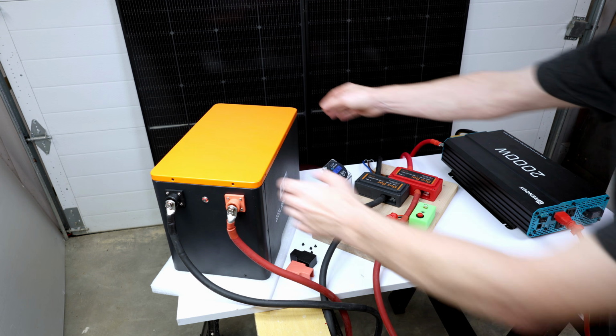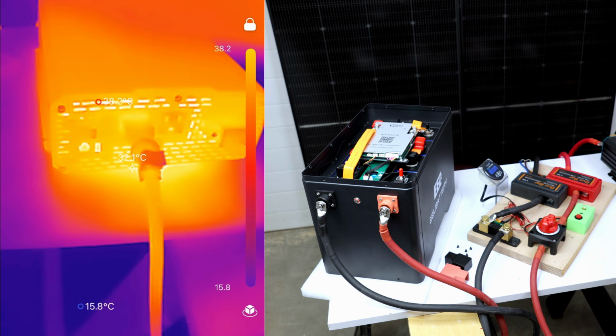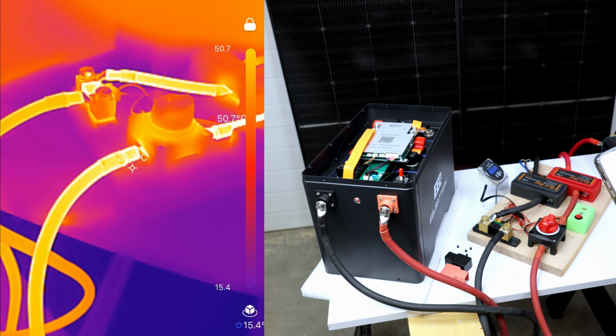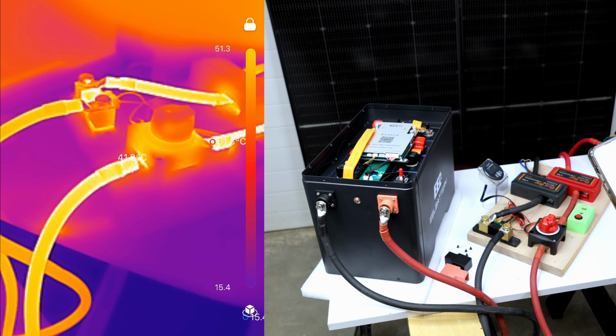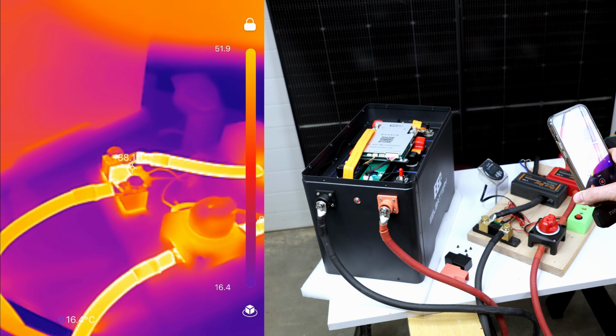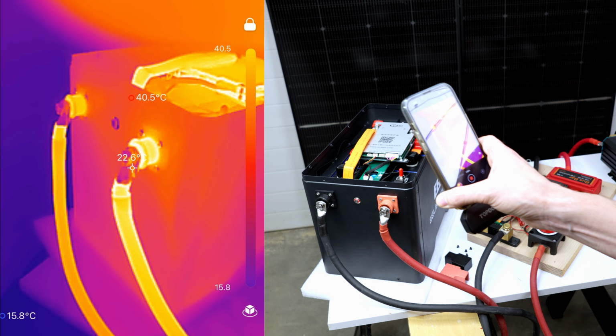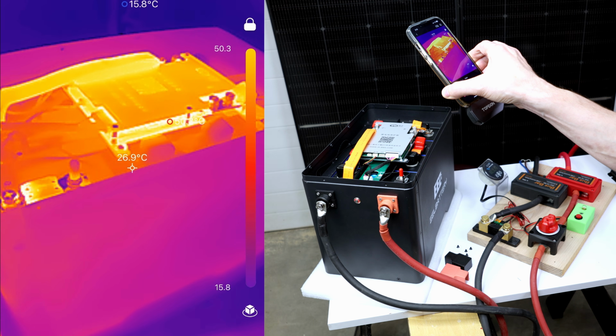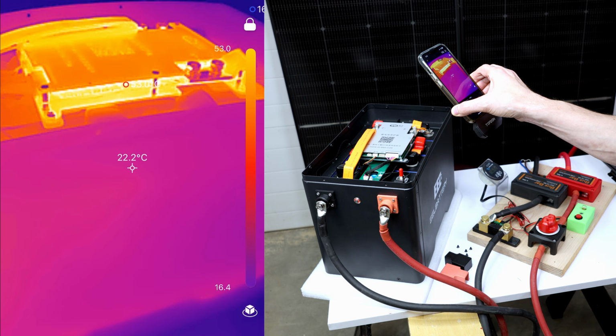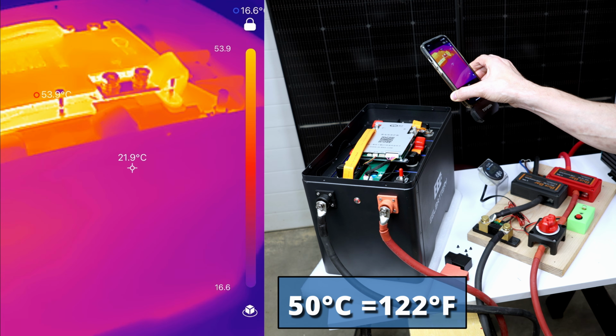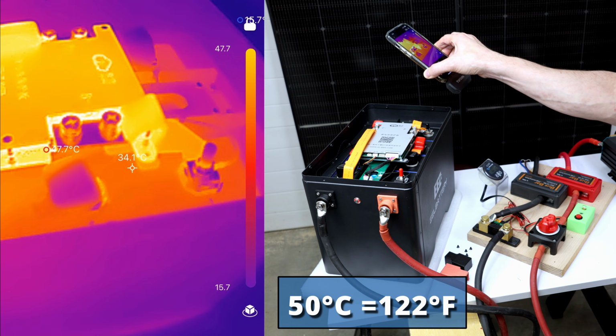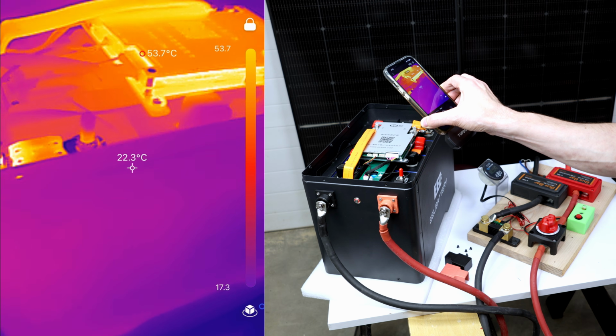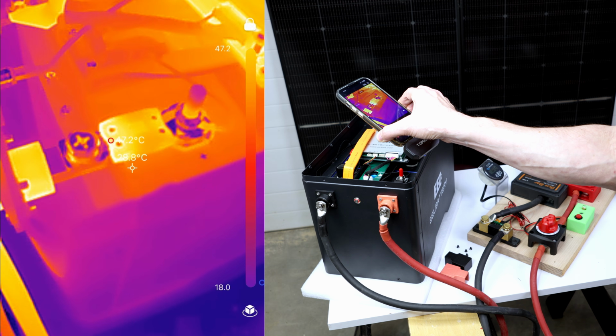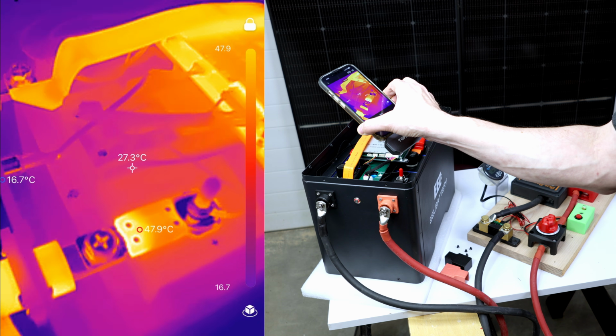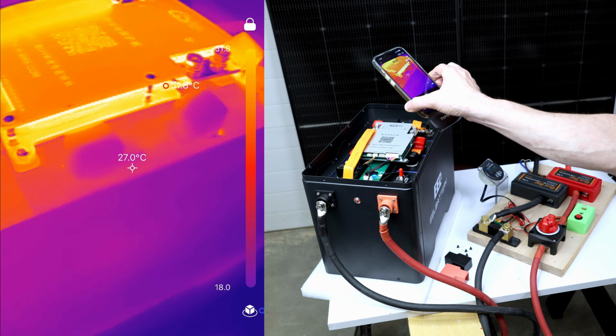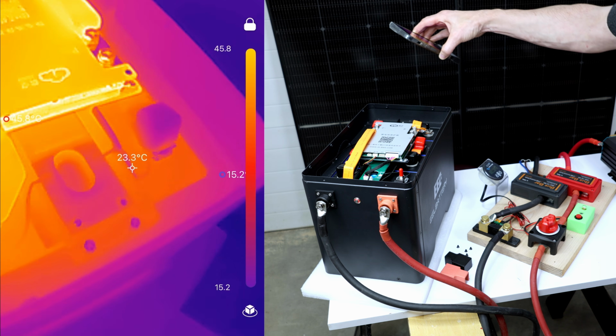The hot spots on the inverter there are 38 degrees Celsius. We have some warm spots, 50 some degrees, on the wiring. The BMS has some warm spots there too, still no more than 50 some degrees Celsius. That's pretty good. You'd expect the fuse to be a little bit warm, but none of our connections are unusually warm, so that's good.